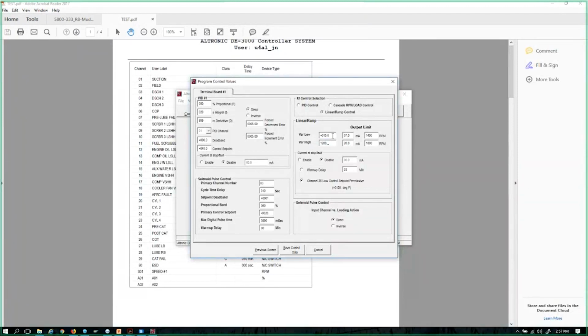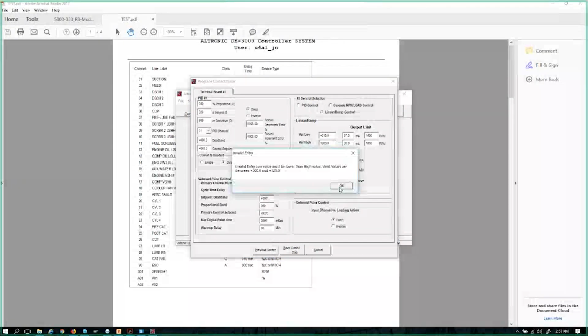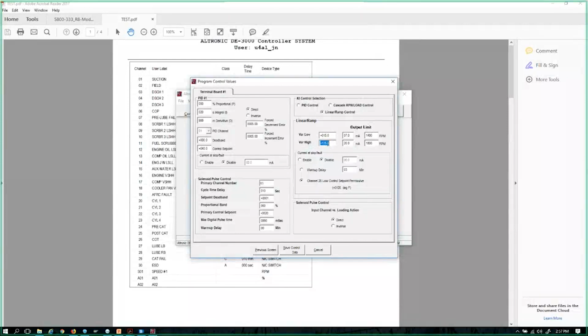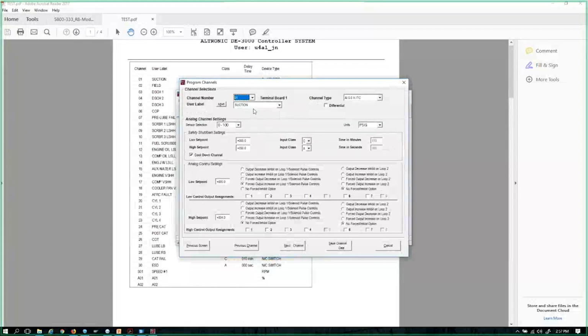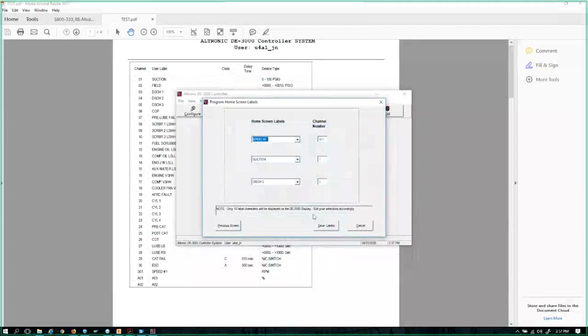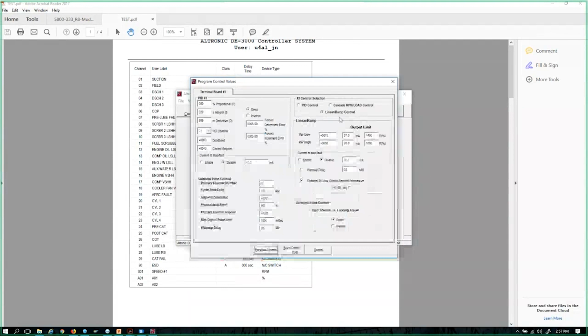I'll put in a high variable of 1200. I'm going to attempt to put a high variable of 1200 in. Oh, you know what? It's not going to let me because my channel is not configured as such. So let's fix that problem. I'll change it to 0 to 2000 real quick. Now it's going to let me put in 1200 for my high pressure. And how about I go with 1000 for my low pressure?